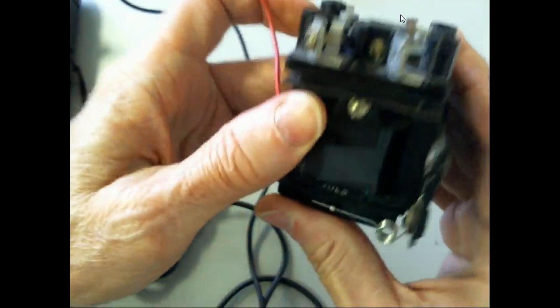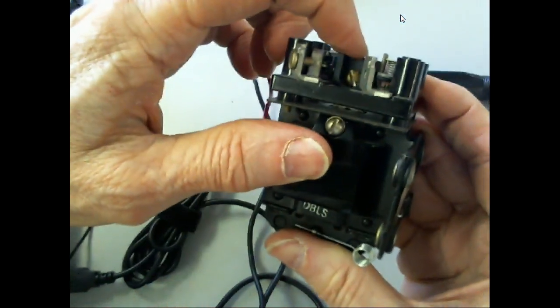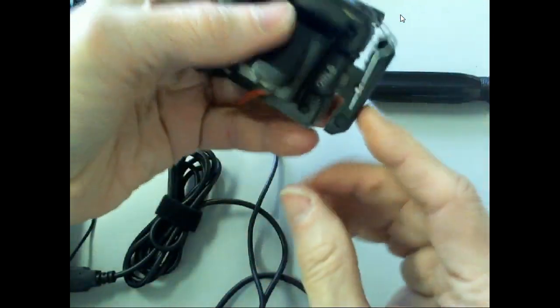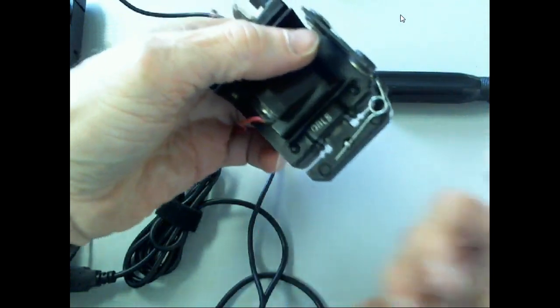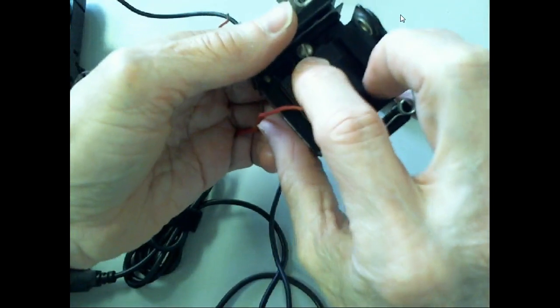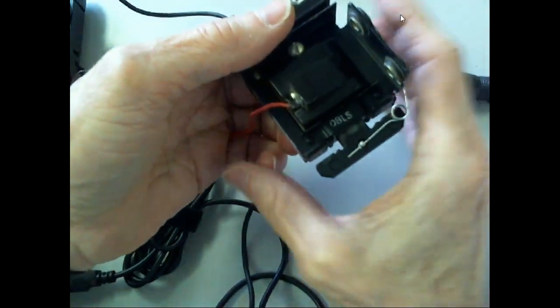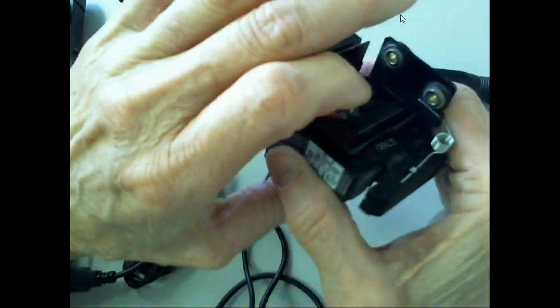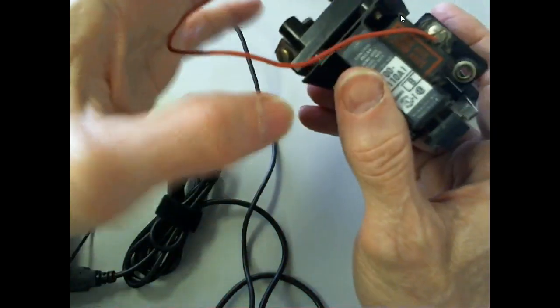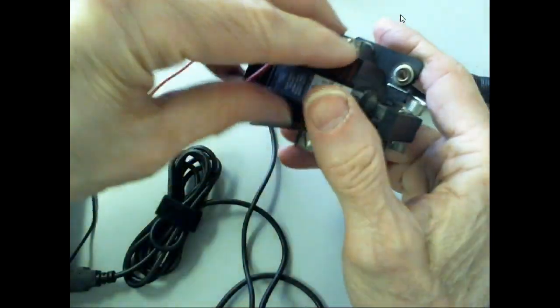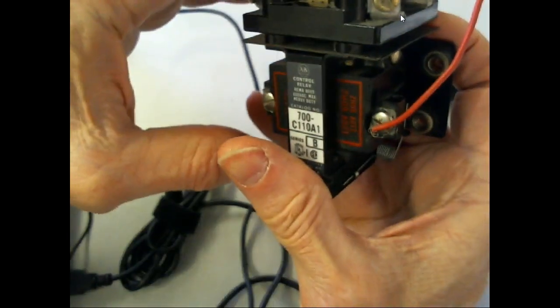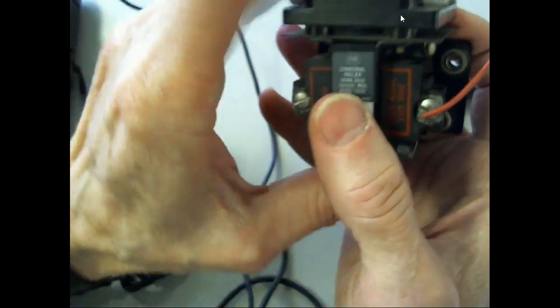But we could break this screw off right here. And then we could come up here and take the springs off, and this armature would pull out. And then we could pull the coil. We could take the screw off right here, and we could pull the coil out. So this one's repairable. If the coil ever gets burned up on this one, we could replace it. Yeah, the coil on this one is rated at 120 volts, 60 hertz.